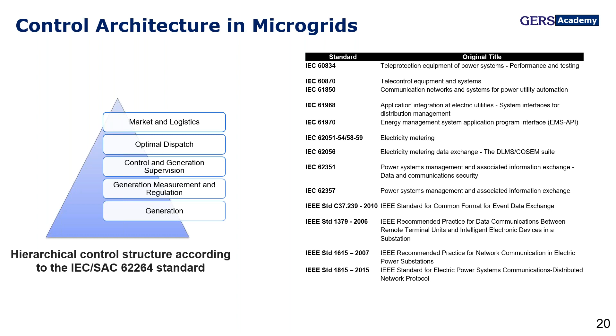Let me show you, in an easier way, that the control architecture in microgrids is split into three main control strategies: primary, secondary, and tertiary control. Primary control seeks the availability of the network to operate even in island mode, and it's noticeable how we implement a control strategy to keep voltage and frequency at proper values. Secondary control seeks the availability to move our stationary point to a different condition.